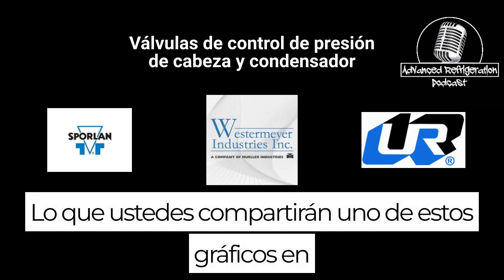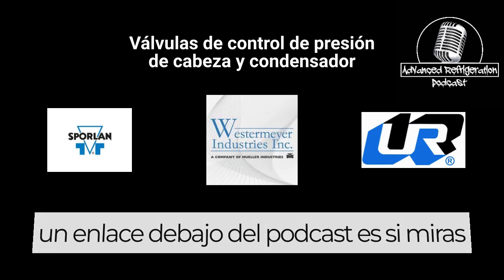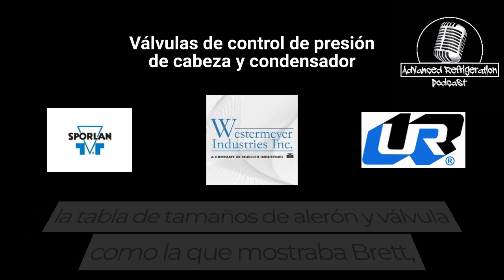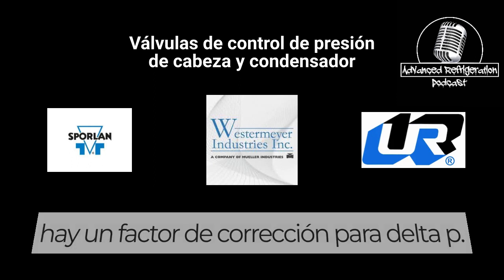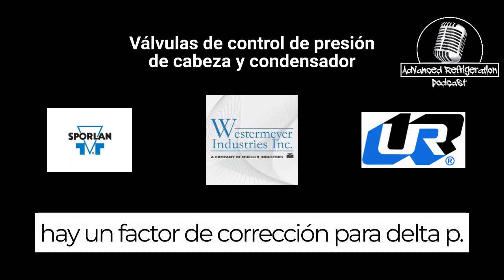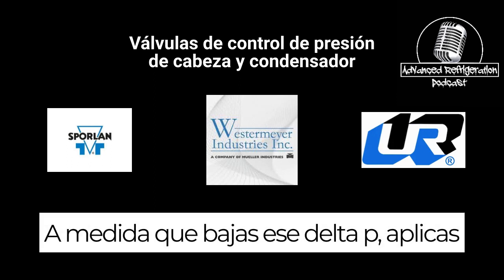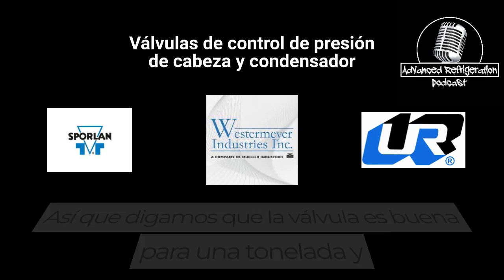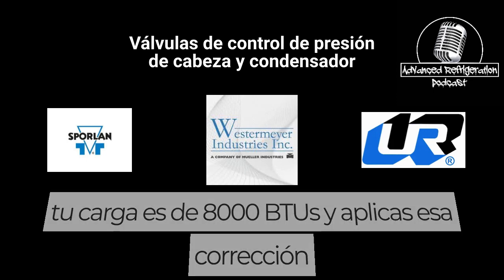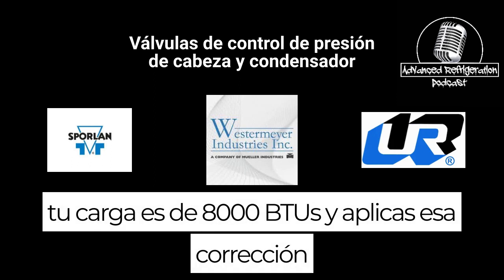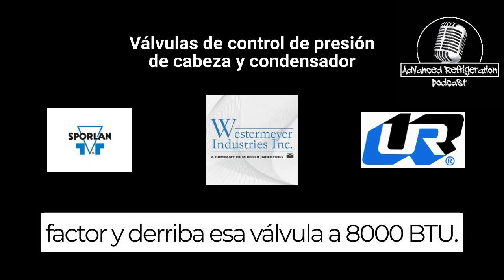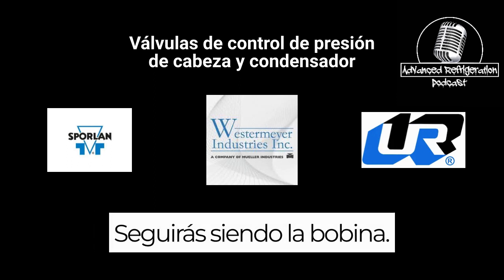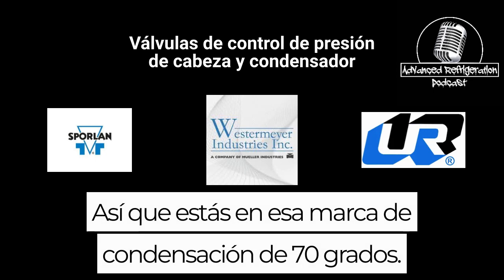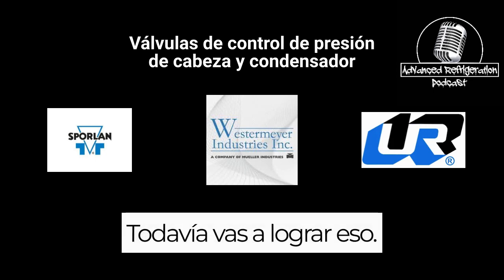We'll share one of these charts in a link with the podcast. If you look at the valve sizing chart like Brett was showing, there's a correction factor for delta P. As you lower that delta P, you apply the correction factor to the valve sizing. So say that valve's good for 1 ton and your load's 8,000 BTUs. And you apply that correction factor and it knocks that valve down to 8,000 BTUs. Okay, you're still good. You're still going to feed the coil. You're still going to accomplish that. So you're at that 70 degree condensing mark. You're still going to accomplish that.